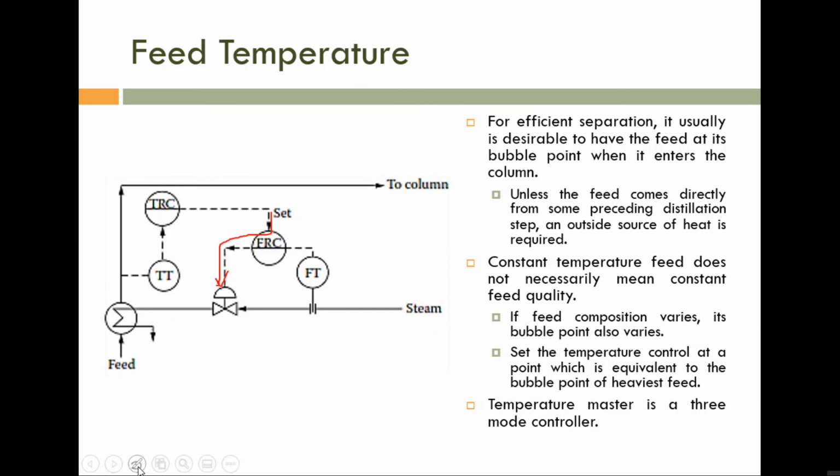Instead of using a simple temperature controller, we have to use a cascade controller where the primary control loop is temperature. The temperature controller is acting as the primary control loop, whose set point is given to the second control loop. That one is nothing but the steam flow rate control loop. So this one is the flow rate controller, which is used to control the steam flow rate, and is acting as the secondary controller, whose set point is given by the temperature controller. Is it okay?